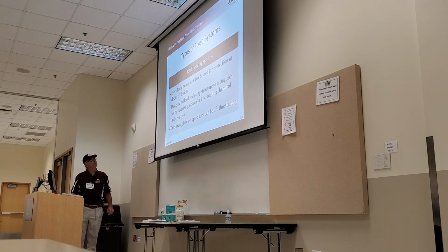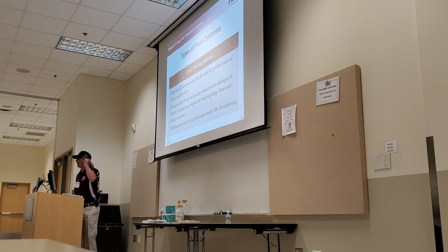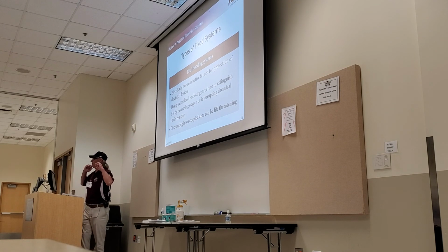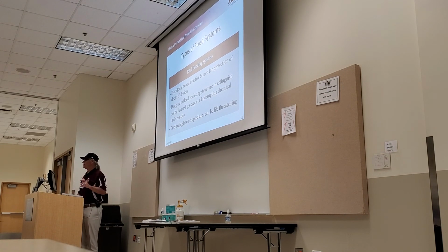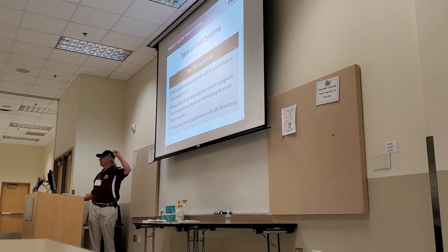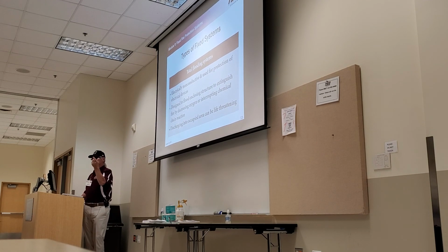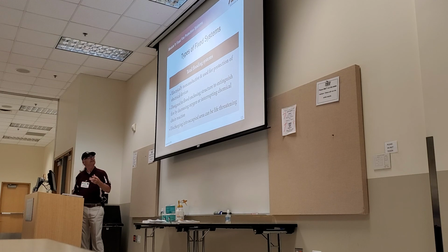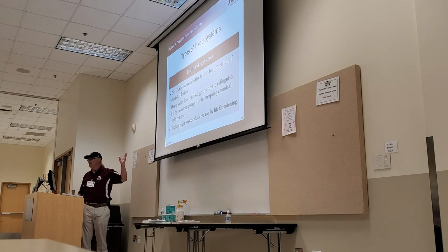So I put in several of these in potato chip plants where you have to have 3 types of devices to warn the people inside. We have a visual, which is a rotating beacon. Then we have these sirens that are good for 2 miles outside. And then an olfactory sensor that when the discharge is fired, it crushes a capsule of wintergreen, and you smell wintergreen, and you see the lights, and then you go out there, and it's like you ate a whole can of snuff.